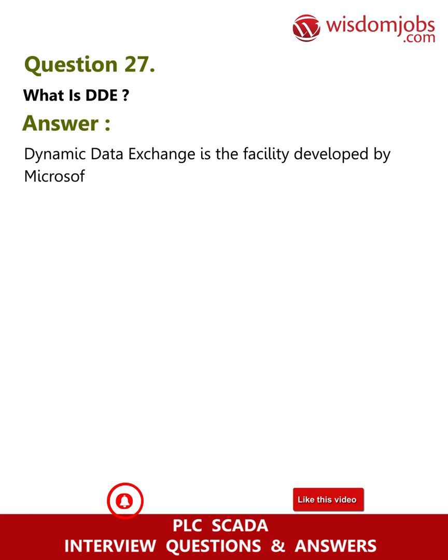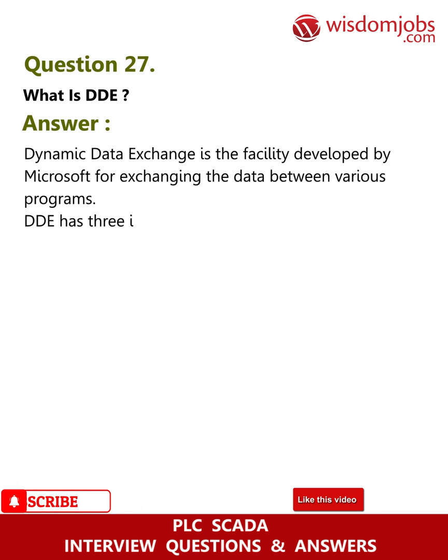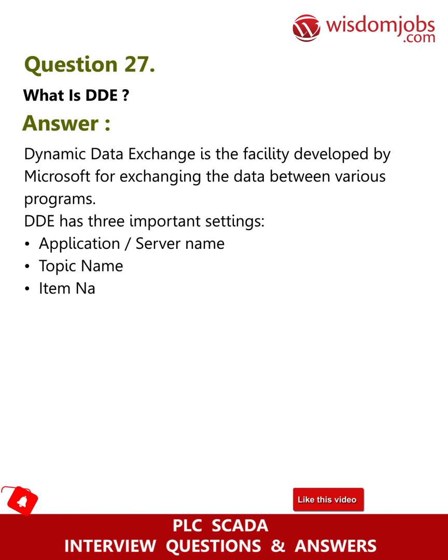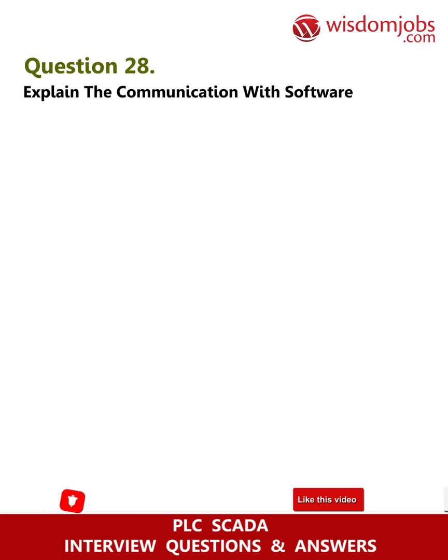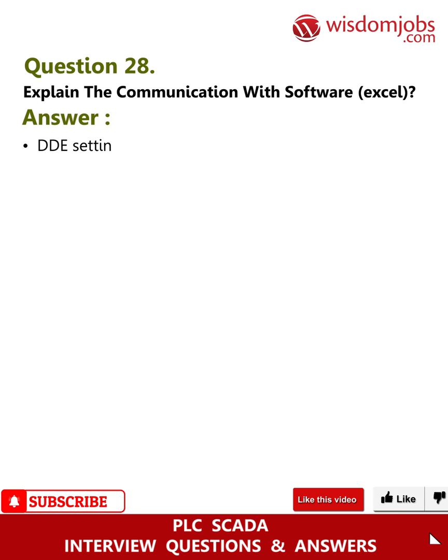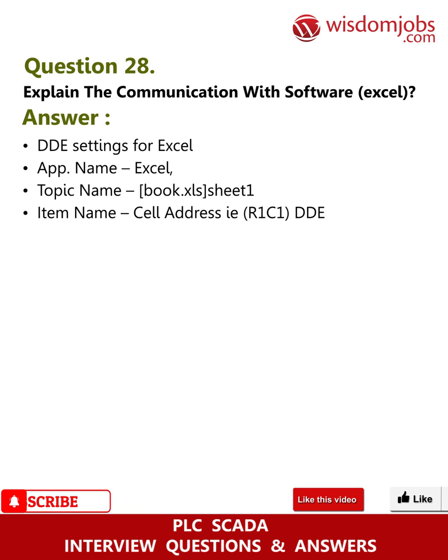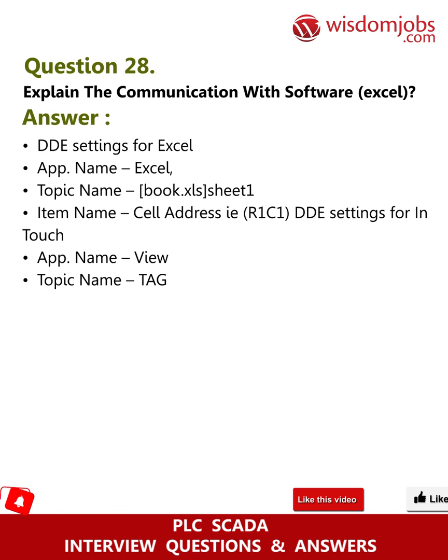Question 27: What is DDE? Answer: Dynamic Data Exchange is the facility developed by Microsoft for exchanging data between various programs. DDE has three important settings: Application (server) name, Topic name, and Item name. Question 28: Explain communication with software Excel. Answer: DDE settings for Excel — App name: Excel; Topic name: [Book.xls]Sheet1; Item name: cell address (e.g., R1C1). DDE settings for InTouch — App name: View; Topic name: Tagname; Item name: name of tag.